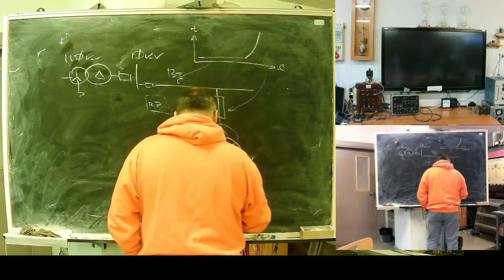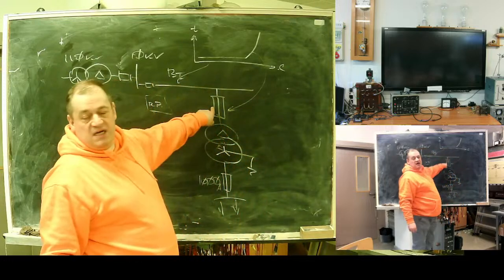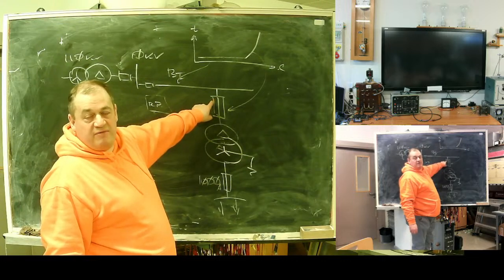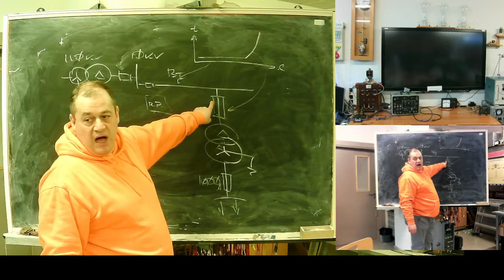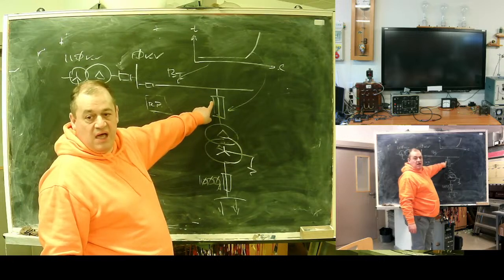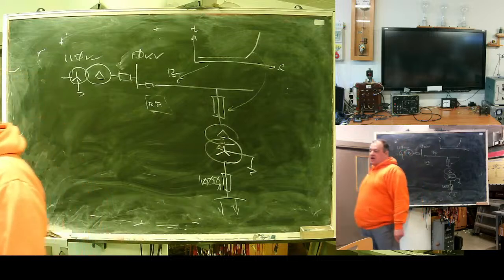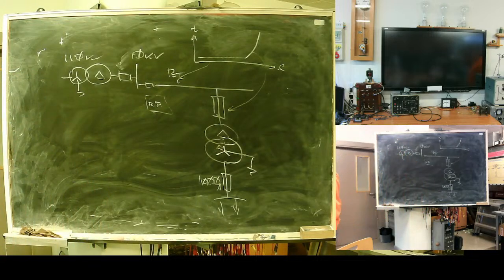Harsh reality: these fuses are unreliable. 10, 11 kilovolt fuses are not precise and are often poorly prepared. They do not hold their characteristics. They are often mounted openly and can lose their water tightness.